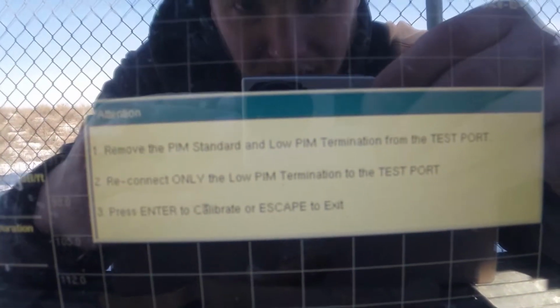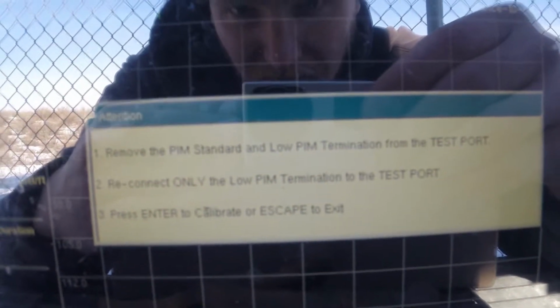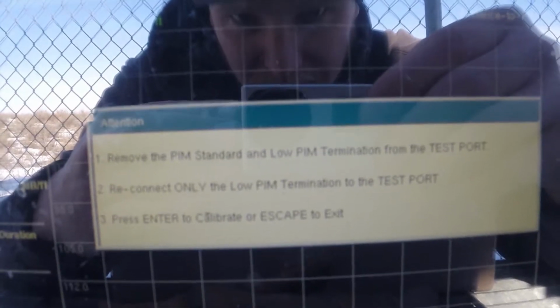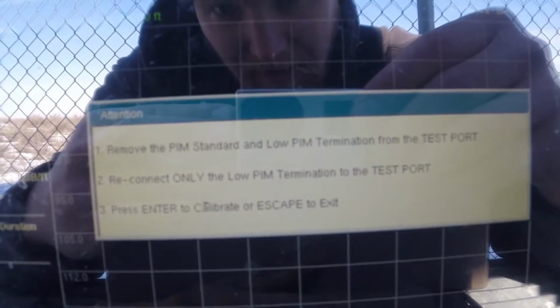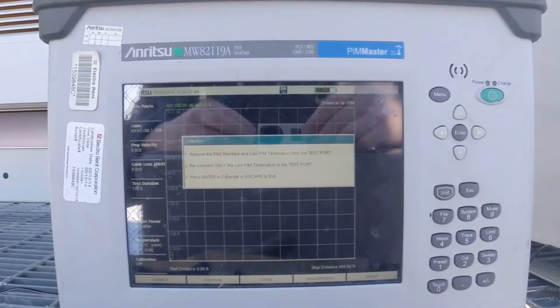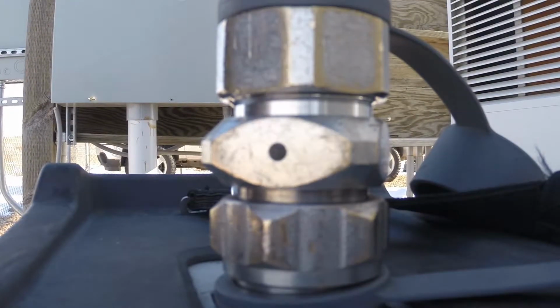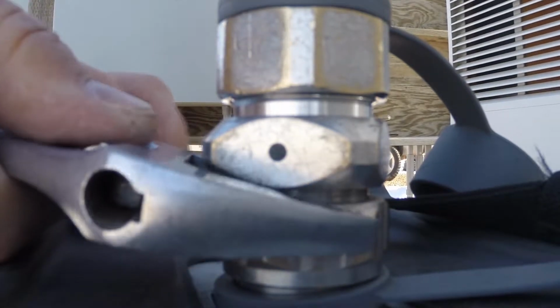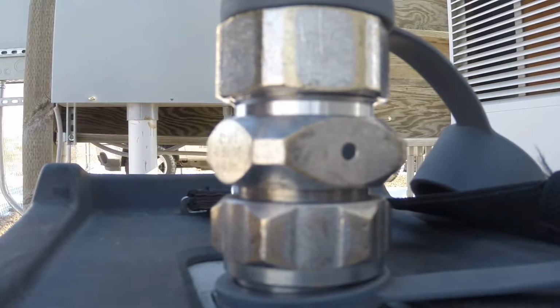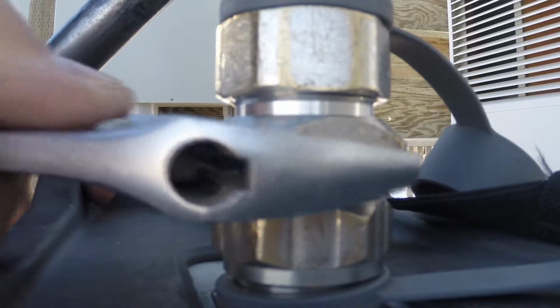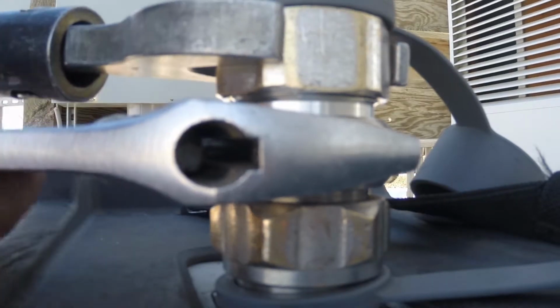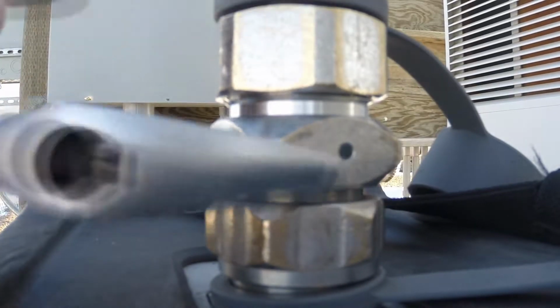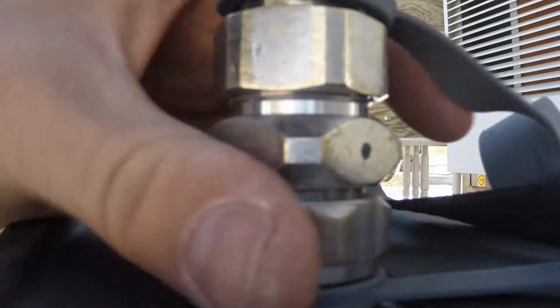So once that first portion is done, it says remove PIM standard and low PIM termination from the test port. Reconnect only the low PIM termination to test port. Press ENTER to calibrate or ESCAPE to exit. So again, up here, loosen my standard, hold the square portion of the standard, and untorque my PIM load.